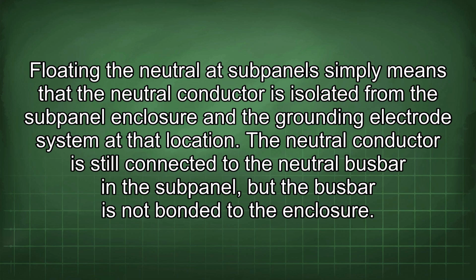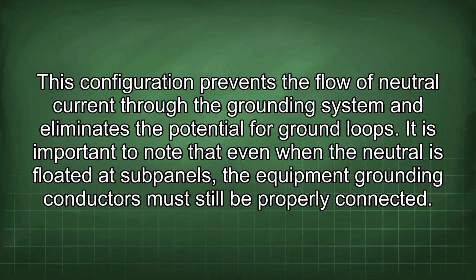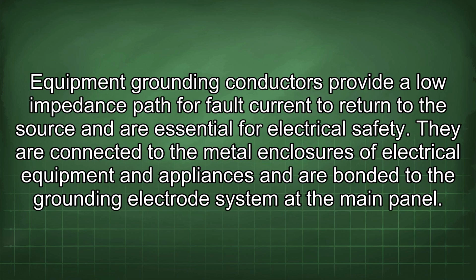Floating the neutral at a subpanel simply means that the neutral conductor is isolated from the subpanel enclosure and the grounding electrode system at that location. The neutral conductor is still connected to the neutral busbar in the subpanel, but the busbar is not bonded to the enclosure. This configuration prevents the flow of neutral current through the grounding system and eliminates the potential for ground loops. It is important to note that even when the neutral is floated at subpanels, the equipment grounding conductors must still be properly connected. Equipment grounding conductors provide a low impedance path for fault current to return to the source and are essential for electrical safety.